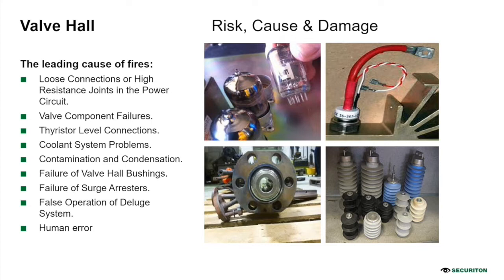Then we have coolant system problems. It is generally accepted that water is the best coolant, a very effective medium to remove heat losses. These heat losses basically come from the HVDC thyristor valves. So water combines several characteristics, and we all know these characteristics. If there is a failure of this kind of coolant system, then the chance of fire is very high in this kind of application.